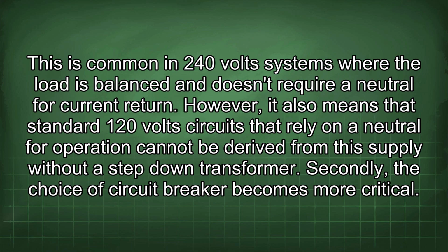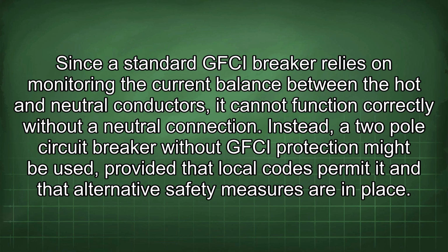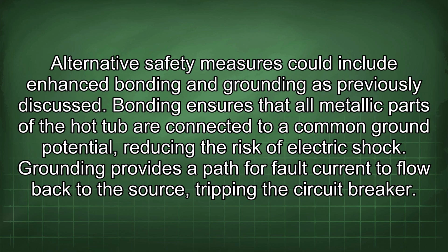Secondly, the choice of circuit breaker becomes more critical. Since a standard GFCI breaker relies on monitoring the current balance between the hot and neutral conductors, it cannot function correctly without a neutral connection. Instead, a 2-pole circuit breaker without GFCI protection might be used, provided that local codes permit it and that alternative safety measures are in place. Alternative safety measures could include enhanced bonding and grounding as previously discussed.